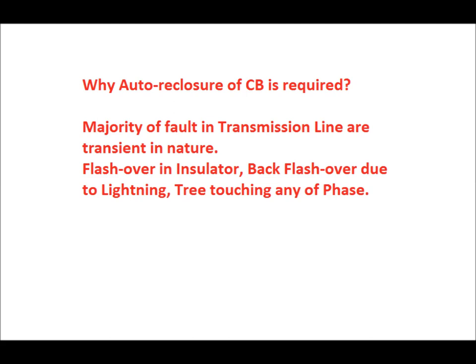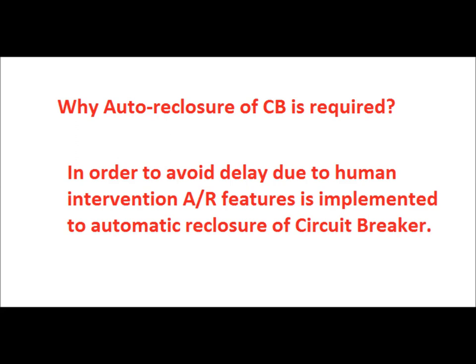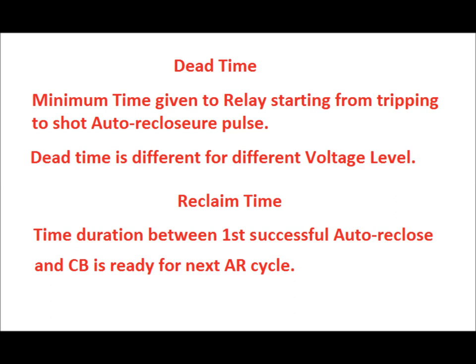In transmission lines, the majority of faults — about 80 to 85 percent — are transient in nature. Examples include flashover of insulators during foggy season due to low creepage distance, back-flashover due to lightning stroke, or a tree touching any phase of the transmission line. These faults clear after the breaker trips, so to maintain stability, automatic reclosing is required to avoid the time delay caused by human intervention.